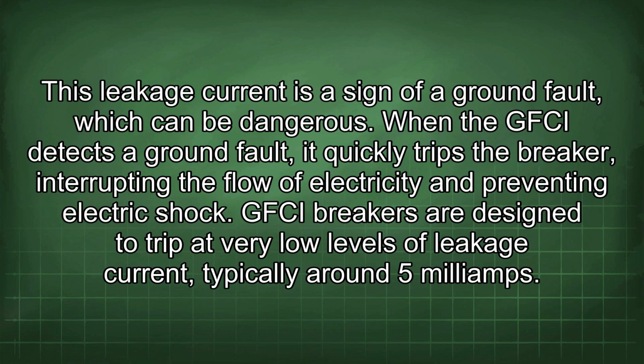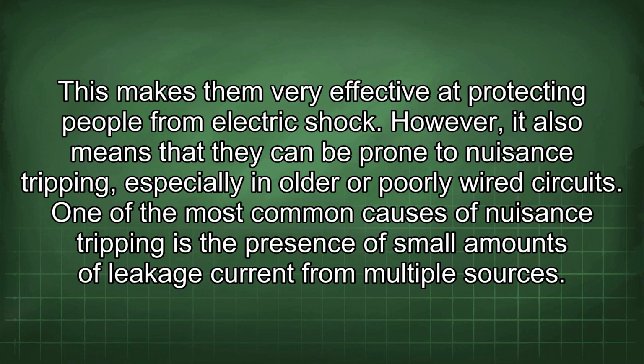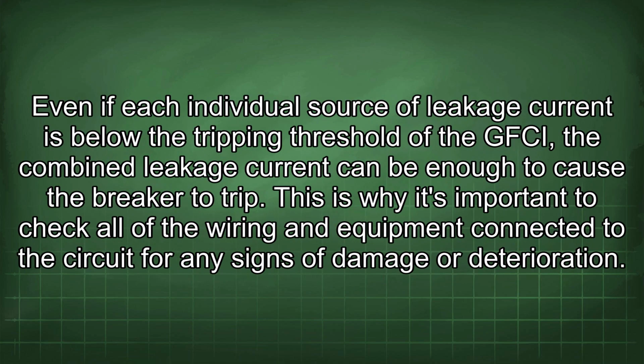When the GFCI detects a ground fault, it quickly trips the breaker, interrupting the flow of electricity and preventing electric shock. GFCI breakers are designed to trip at very low levels of leakage current, typically around 5 milliamps. This makes them very effective at protecting people from electric shock. However, it also means that they can be prone to nuisance tripping, especially in older or poorly wired circuits. One of the most common causes of nuisance tripping is the presence of small amounts of leakage current from multiple sources. Even if each individual source of leakage current is below the tripping threshold of the GFCI, the combined leakage current can be enough to cause the breaker to trip.